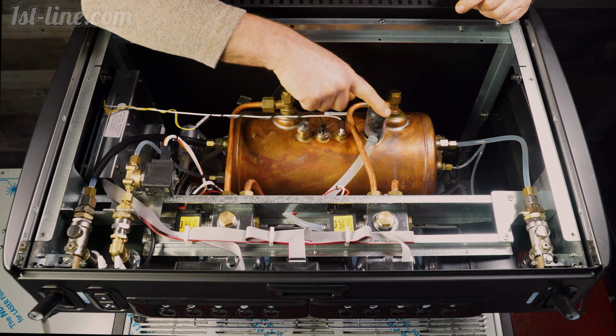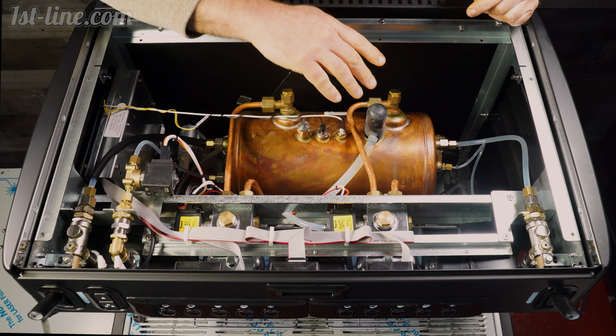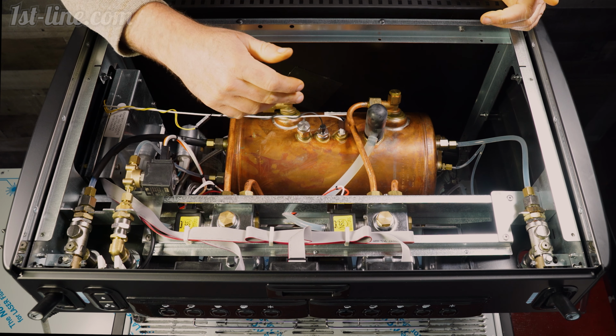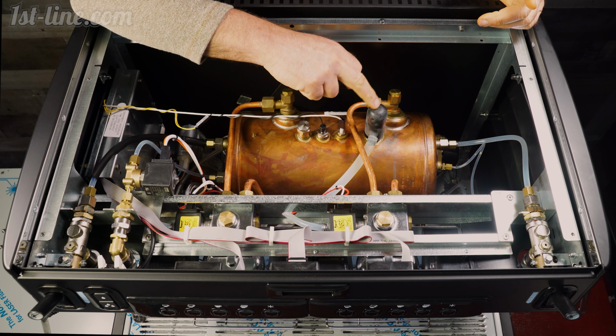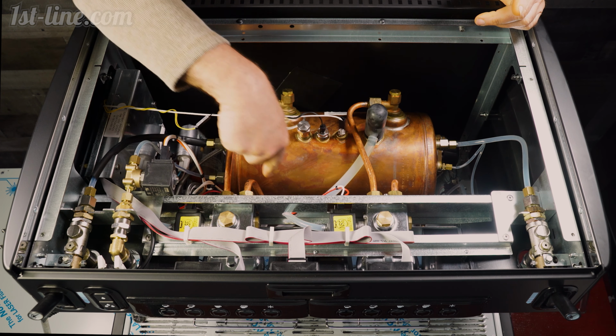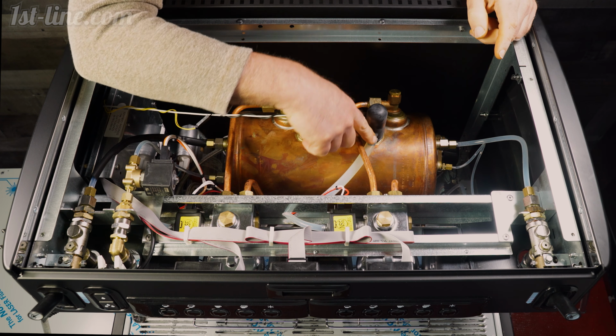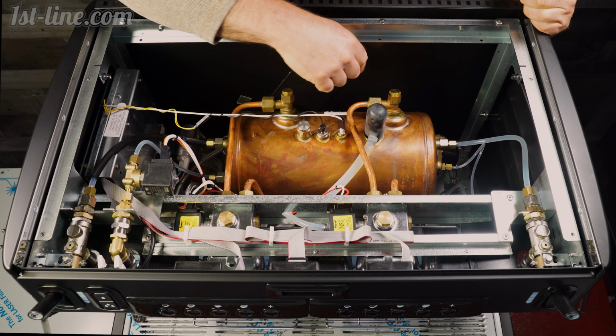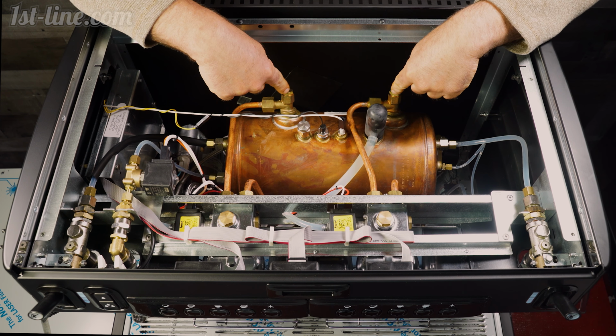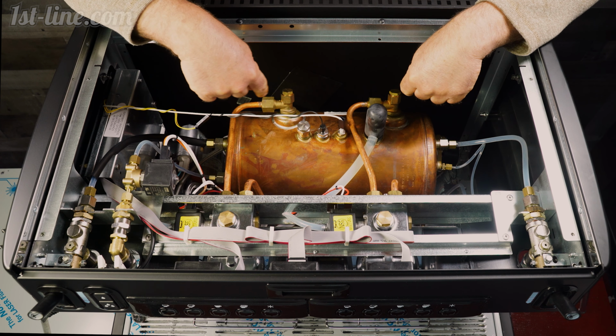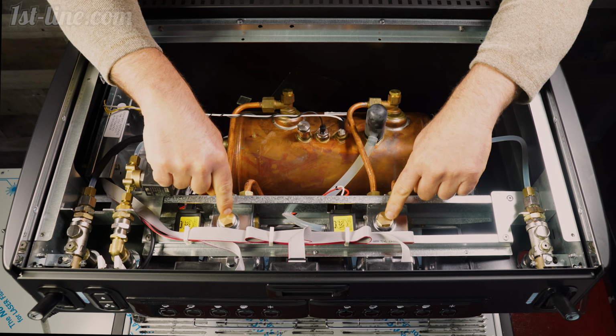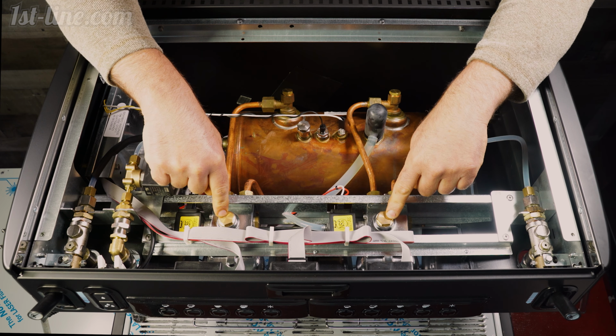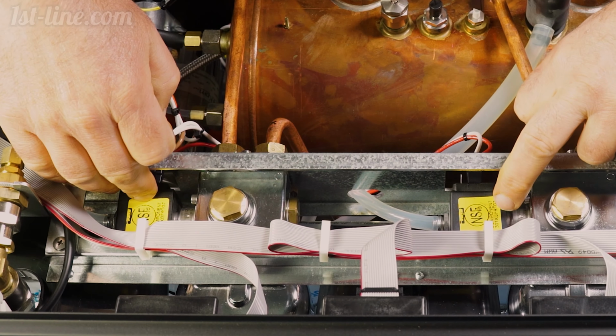Okay, safety valve here. This one is covered nicely because in case the machine goes into an overheat and excess steam starts coming out, this will get redirected to the drip tray. So there is a vinyl hose there. You have clean out nuts here for the heat exchange pipes. And then you'll have clean out nuts on the group heads here as well. And you'll see the solenoid valves.